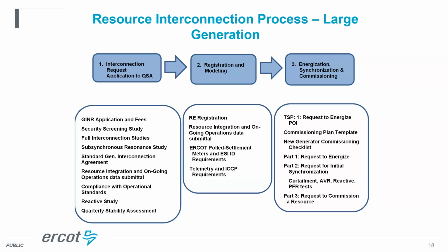Part 2 is request for initial synchronization. This is where they start generating, or if they're a battery, where they start charging. Once they've got part 2 and are cleared to go to their full size, they have to do some testing: curtailment testing, automatic voltage regulation testing, reactive testing, and primary frequency response testing. Once they've passed all those tests, they can submit part 3, which is a request to commission the resource, and this is the exit out of the interconnection process.